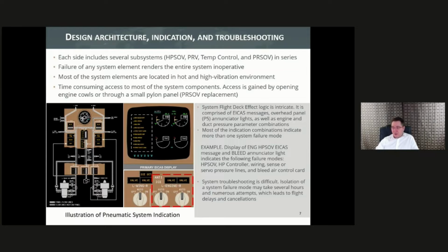So here is the design architecture, indication, troubleshooting of the system. Each side includes several subsystems, like shown before: HPSOV, PRV, temp control, and PRSOV. These are the primary components, just the primary components. There's a lot more, which trigger indication in the cockpit and air supply module. Failure of any system element renders the entire system inoperative, which creates a heavy impact on operation.